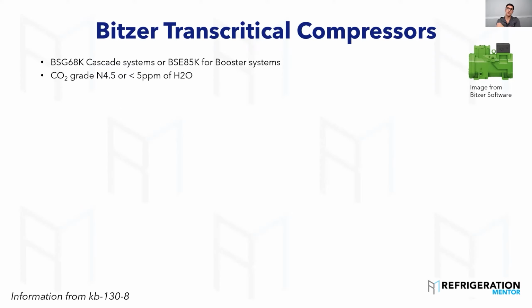Okay, CO2 grade, this is very important. So Bitzer and Copeland and other manufacturers talk about different grades. Bitzer says they want an N4.5, or less than 5 parts per million of water. So this is above Coleman grade 4. It's the next level up. Coleman grade, which Copeland recommends, is grade 4. They call it Coleman grade, and that's less than 10 parts per million.